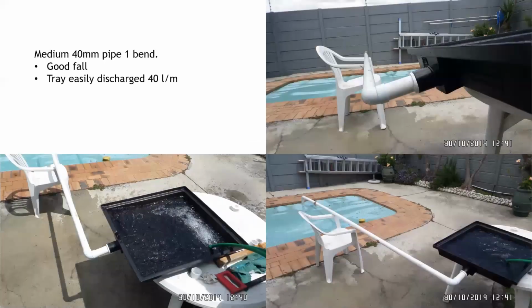So if you have a look at a 40 mil pipe with one bend, it's got good fall. You can see that fall on the top right-hand side there. It falls straight away from the drip tray and off it goes, and it easily discharged the 40 liters a minute. So there's a 40 mil pipe with a 90-degree bend, about 3.5 meters long. But it's got a good fall and it goes like a bomb. It actually creates a little bit of a Venturi effect.